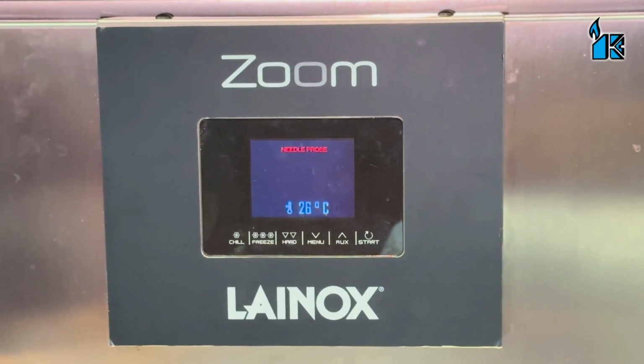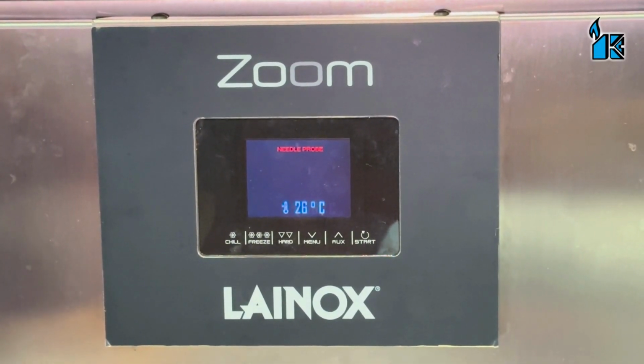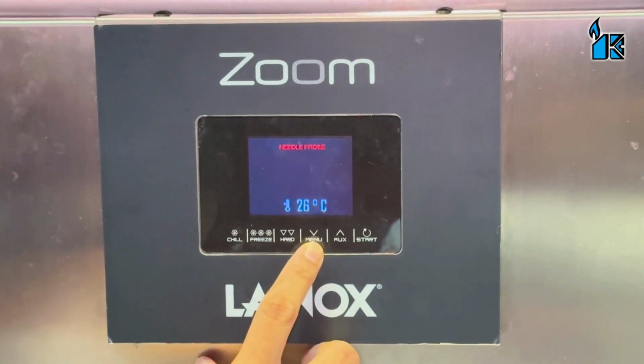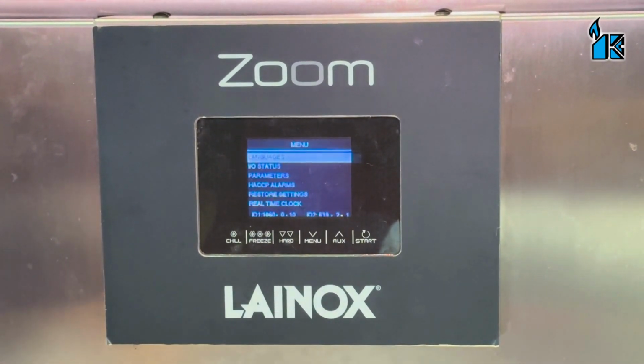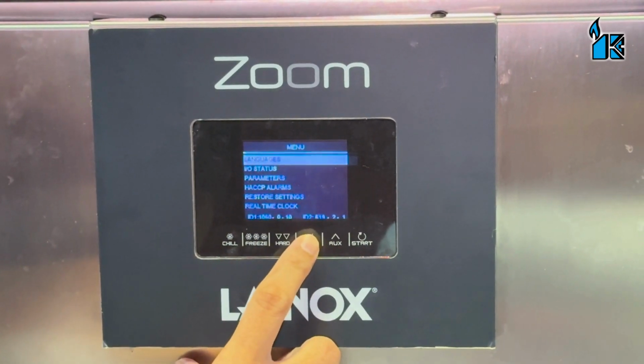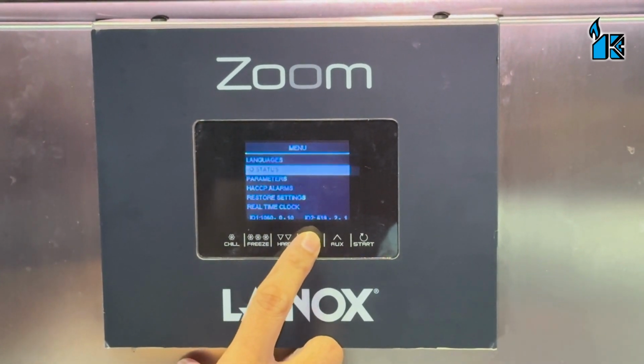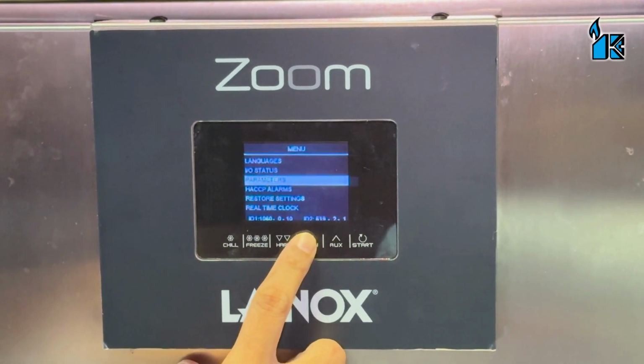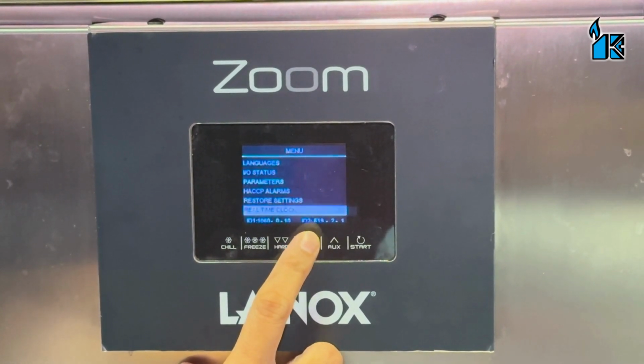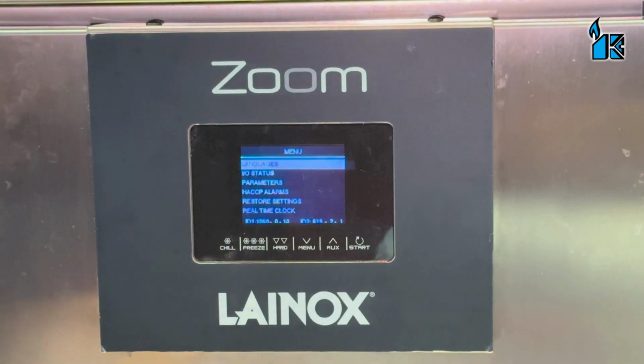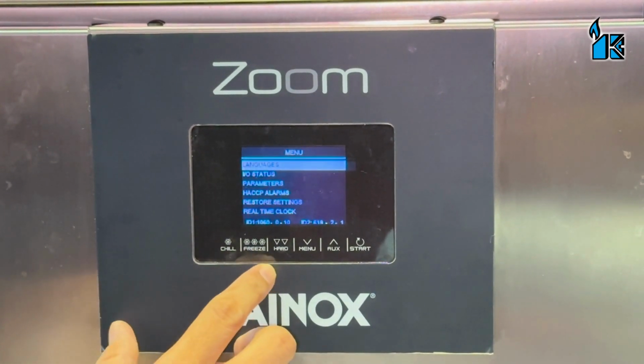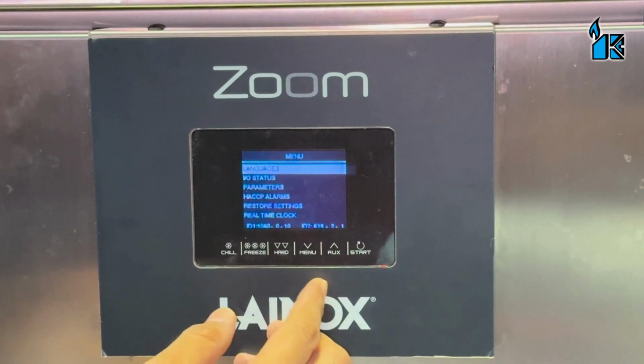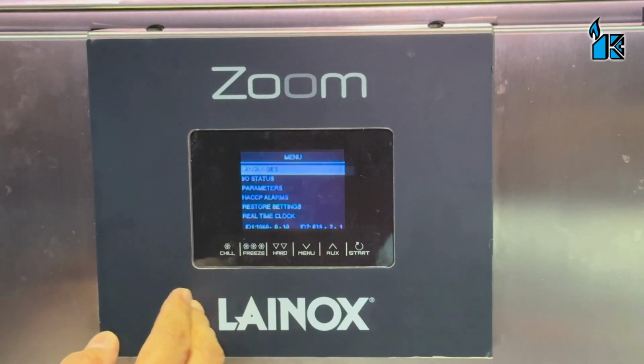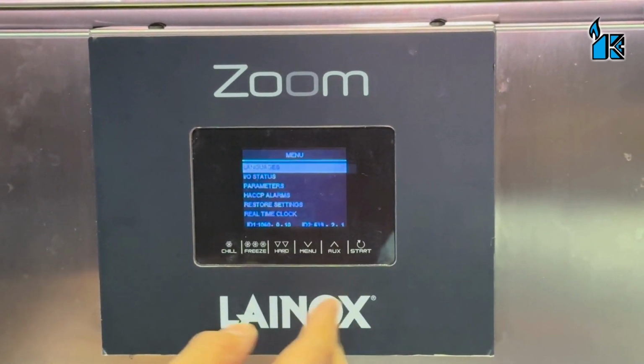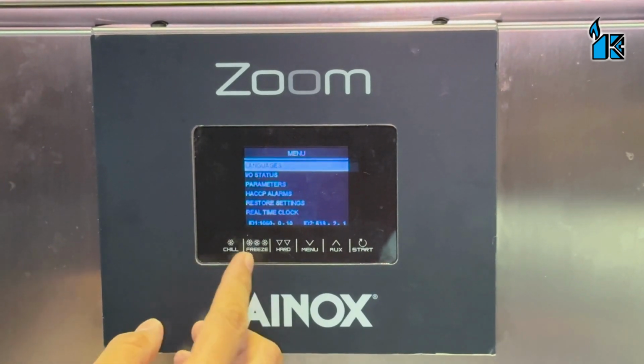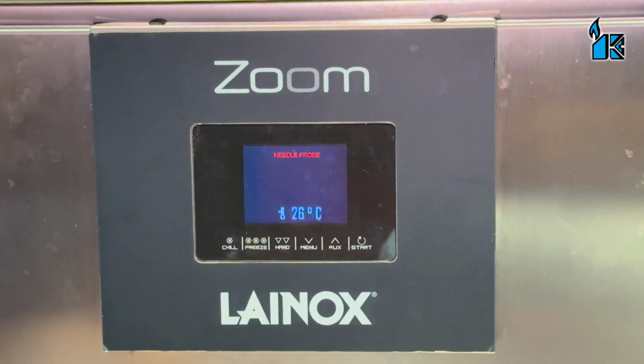Before you start, to get to know your machine, you can set the menu. You can press the menu. The menu is the common setting for the machine. For example, language, status, parameter, HACCP alarms, restore setting, time and date. So there are 6 common settings for the machine. If you want to go back to the main panel, just leave it for 15 seconds, or you can press the chill mode to go back to the front page.